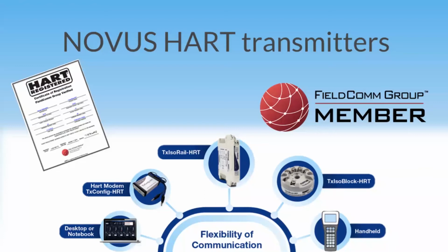These devices are fully compatible with HART devices worldwide and are compatible with HART versions 5 up to 7. Beyond the benefits of HART features, these devices, which are temperature transmitters, are galvanic isolated, 1.5 kilovolts RMS between input and output, and have high accuracy measurement.